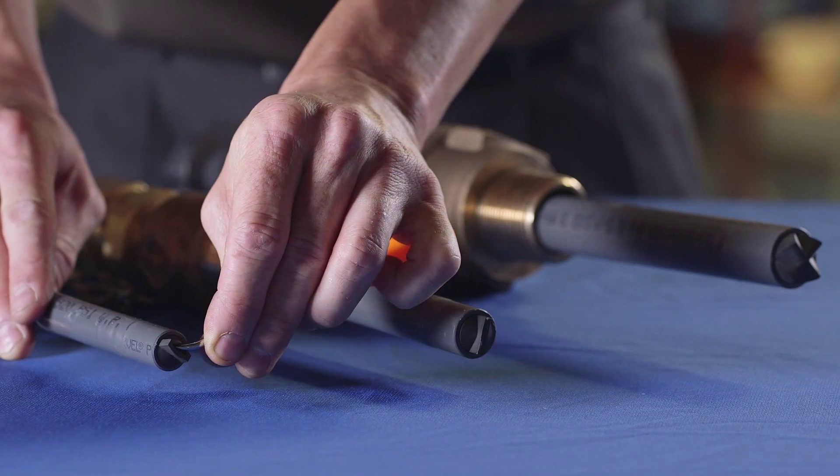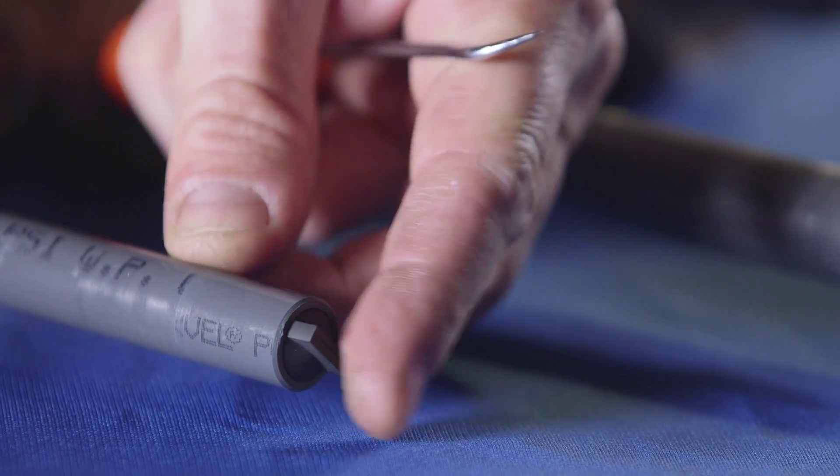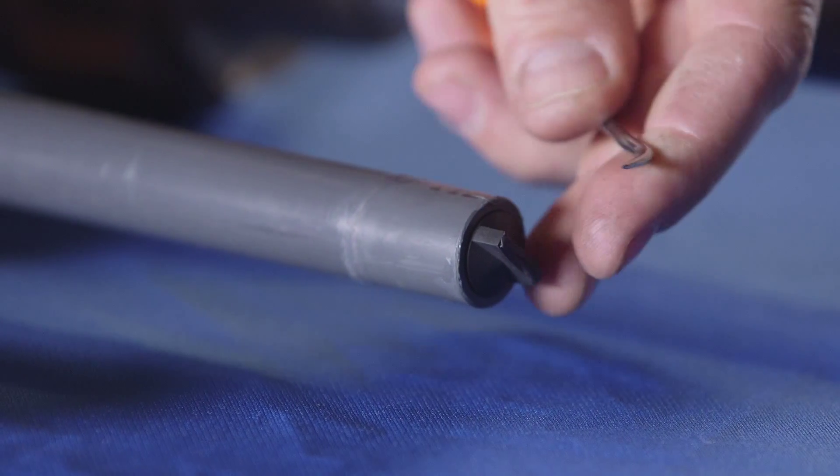Safety Seal extrudes open on positive pressure from the pump to release chemicals into the process flow. Adding a Safety Seal tip to an injector will help resist and in some cases even eliminate premature mixing conditions, thereby extending maintenance intervals.